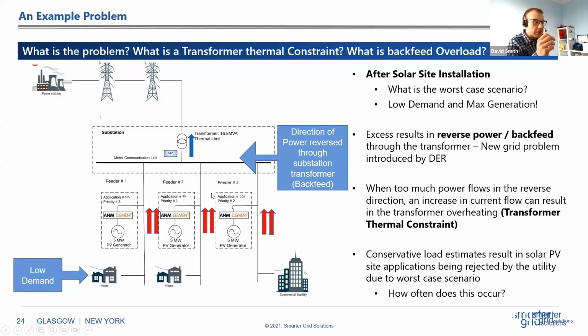And traditionally, there will be maybe once in a year, maybe one day a year where this will happen. But that would mean if all three of these generators want to connect, they need to pay to reinforce that transformer to support that one day a year. And that can be very expensive. And that means it's difficult for some of these generators to connect.